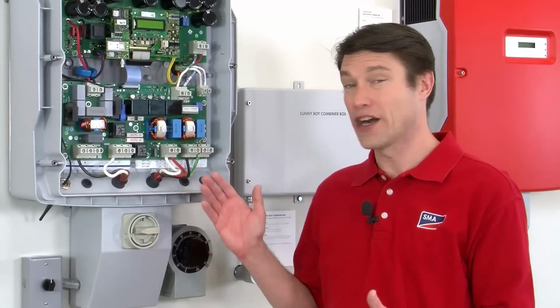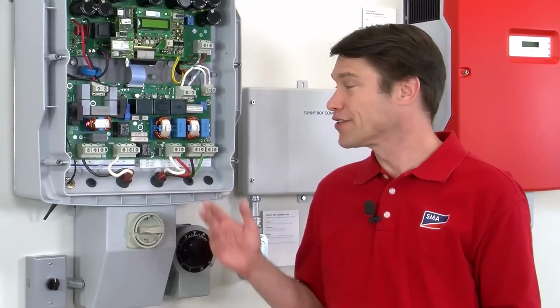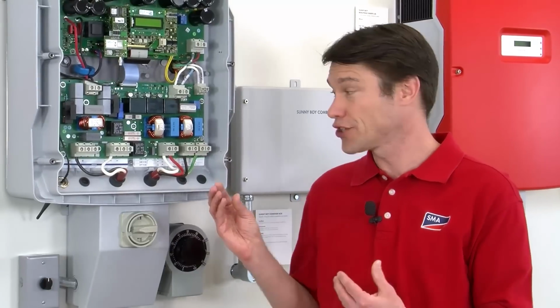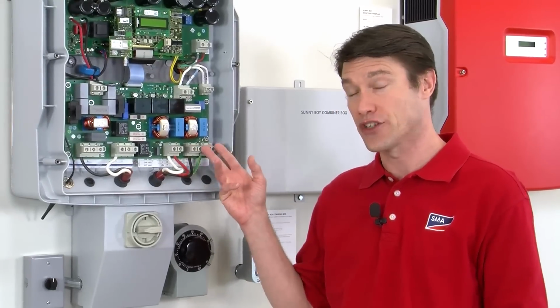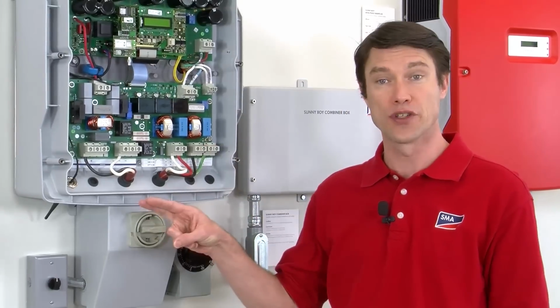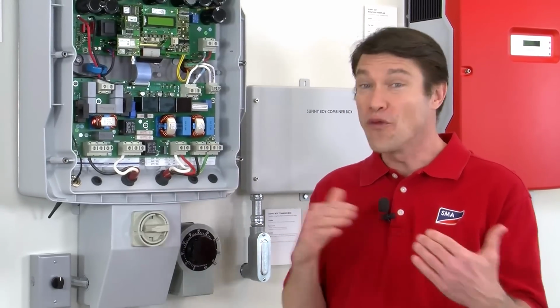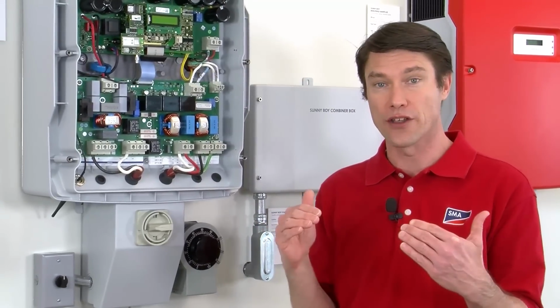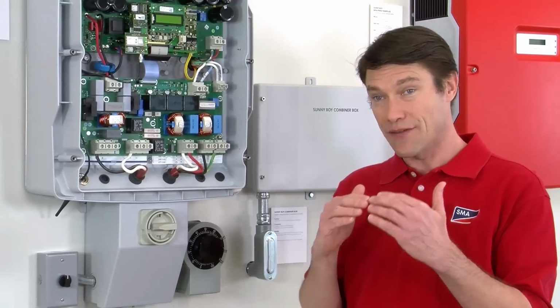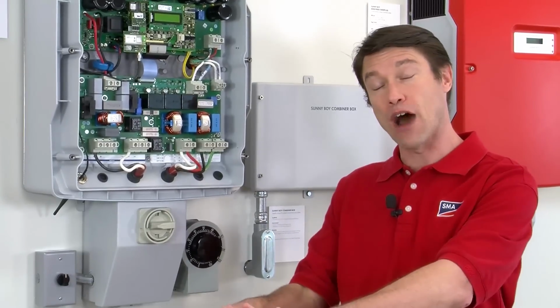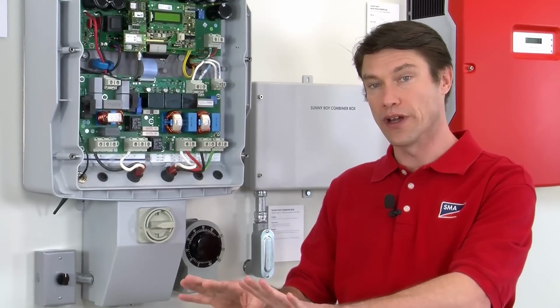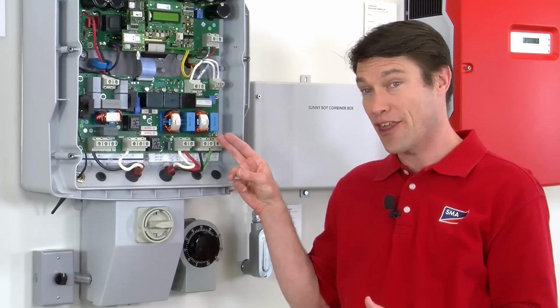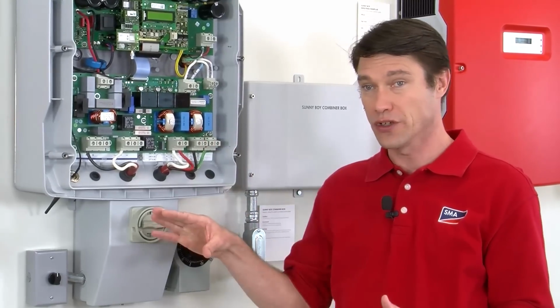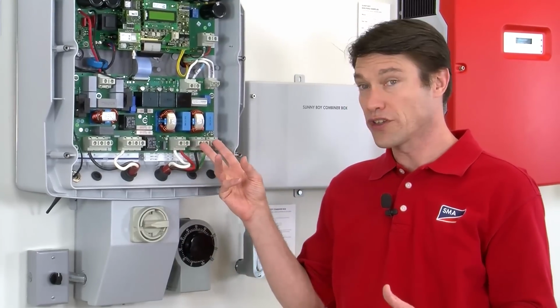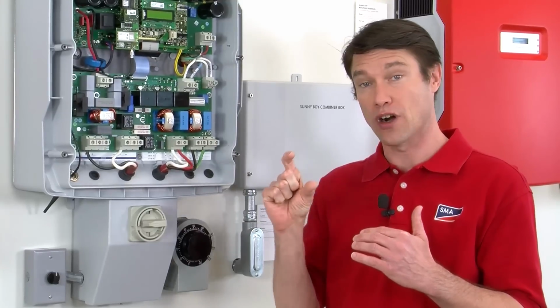Now, the reason loose wiring can lead to a VAC error is that a loose connection will act as a resistor in the path between the AC terminals of the inverter and the utility. So the utility, hopefully, is sitting there right at that nominal value, and the inverter has to have a slightly higher voltage to push its current out onto that utility grid. Now, if there's a resistor in the path between the inverter and the utility grid, the voltage of the inverter has to overcome any drop across that resistor.